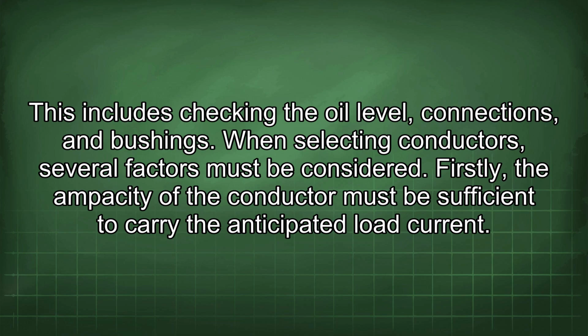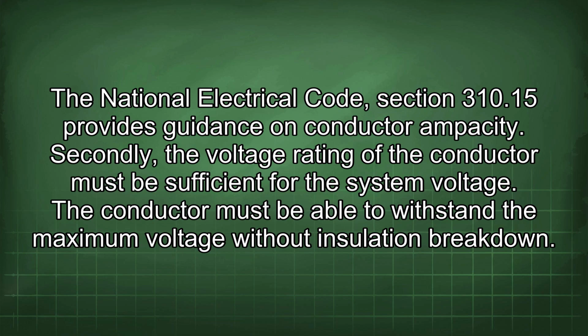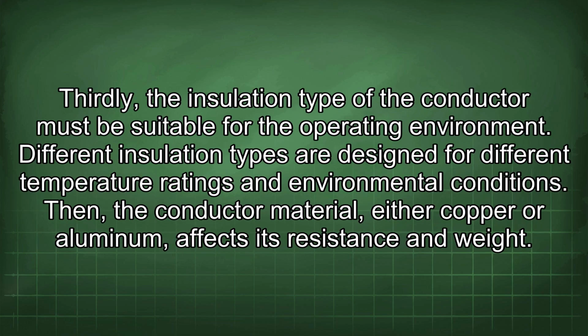When selecting conductors, several factors must be considered. Firstly, the ampacity of the conductor must be sufficient to carry the anticipated load current. The National Electrical Code, Section 310.15 provides guidance on conductor ampacity. Secondly, the voltage rating of the conductor must be sufficient for the system voltage. The conductor must be able to withstand the maximum voltage without insulation breakdown. Thirdly, the insulation type of the conductor must be suitable for the operating environment. Different insulation types are designed for different temperature ratings and environmental conditions.